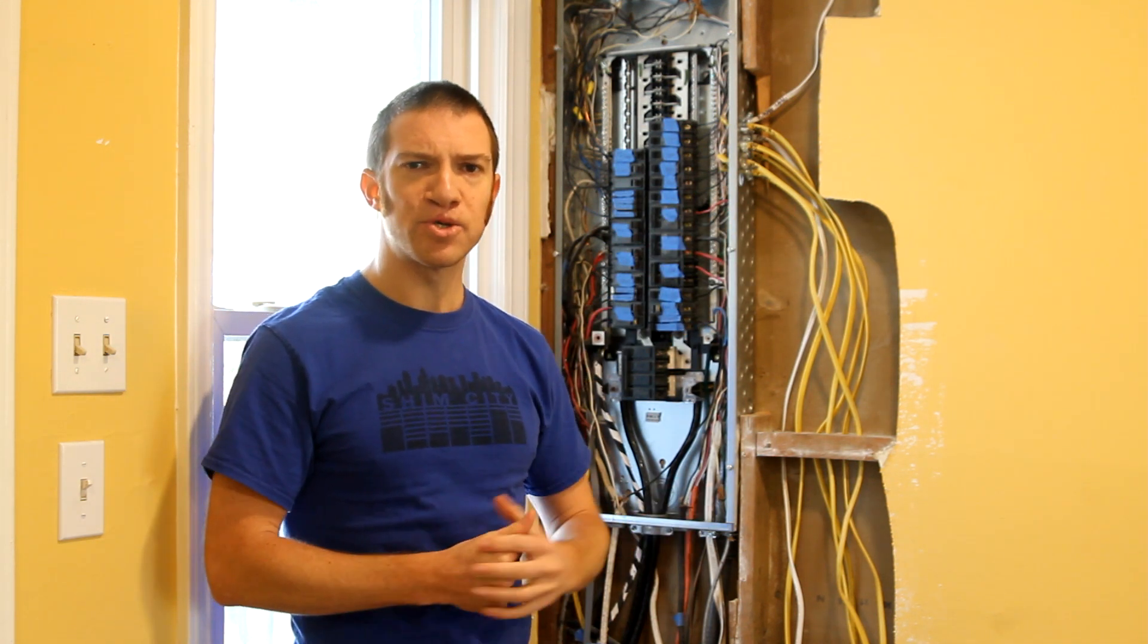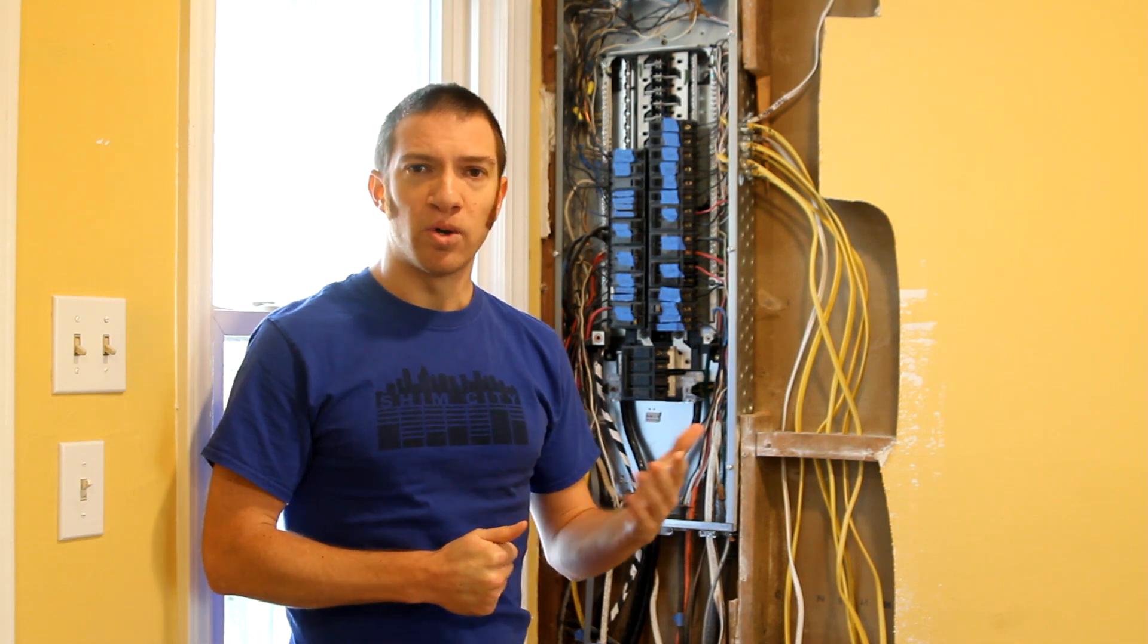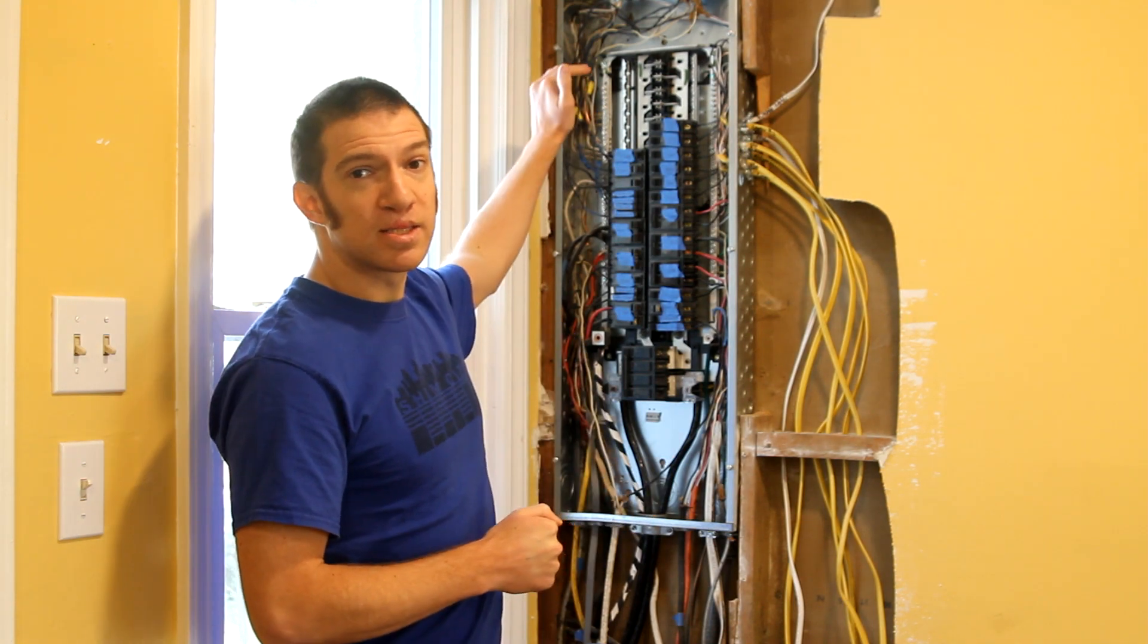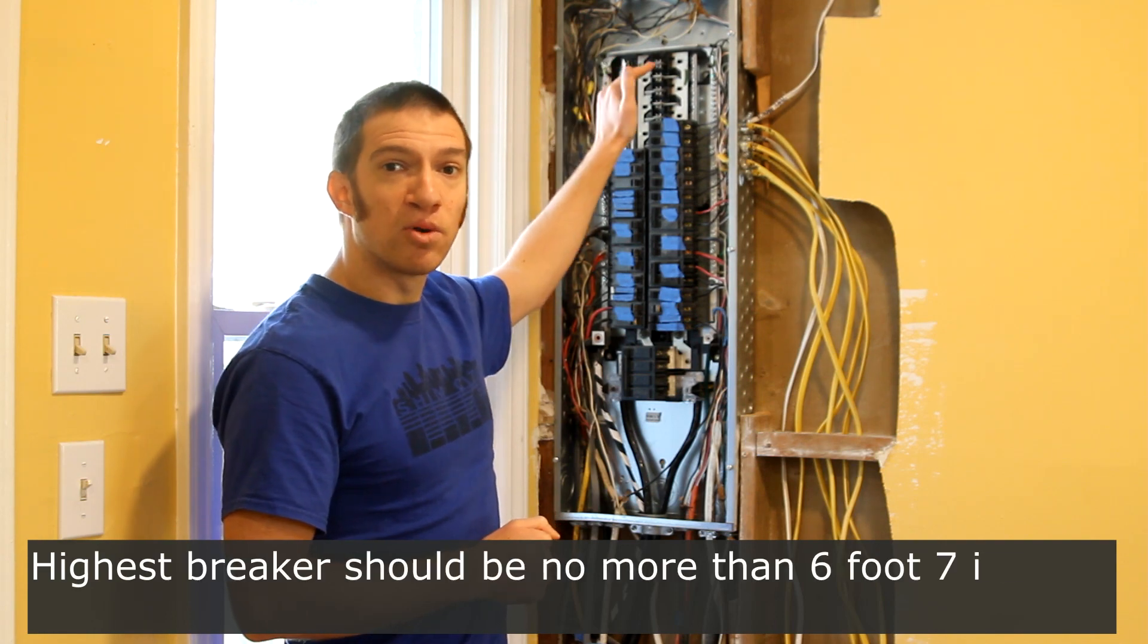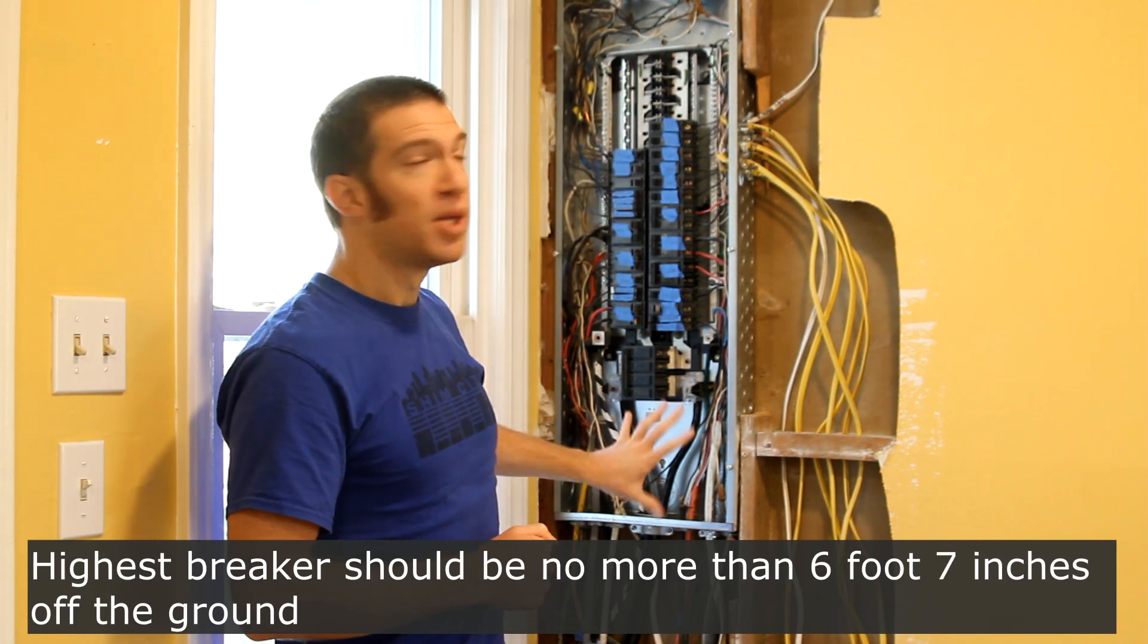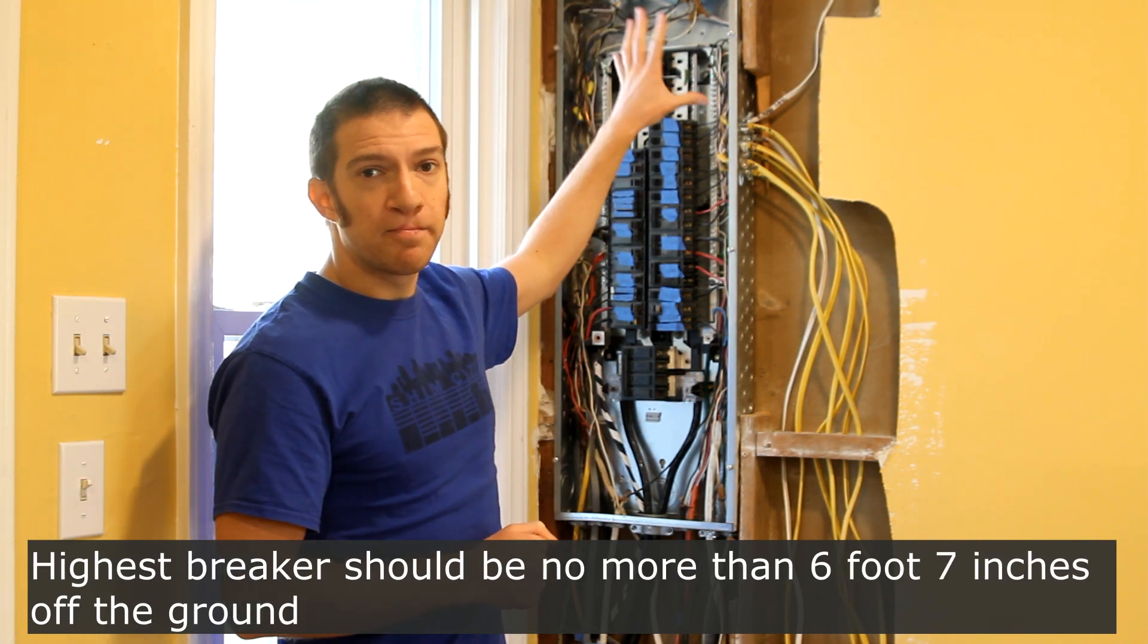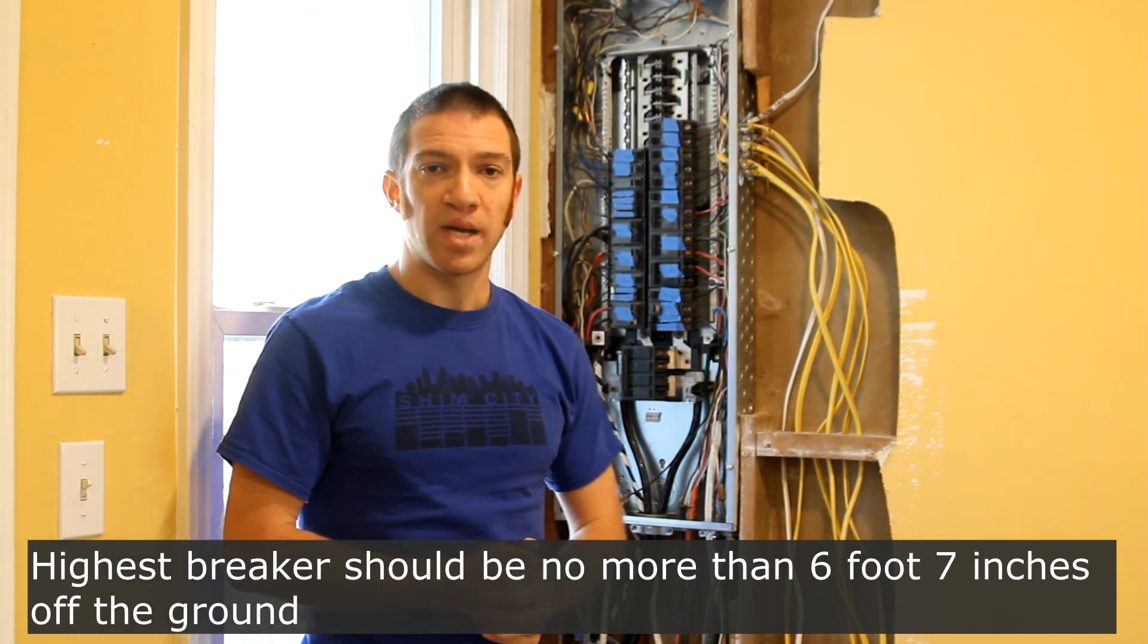When you're installing your final panel, one code requirement that you want to keep in mind is that the tallest breaker on your panel can be no more than six foot seven inches off the ground. So there's no putting it all the way up against the ceiling. Take that into account as well.